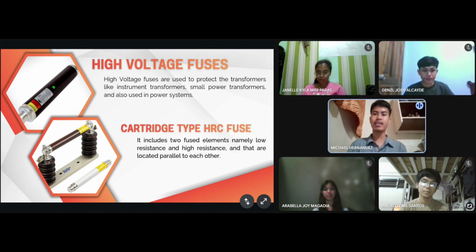Let's talk about the high voltage fuses. High voltage fuses are used to protect transformers like instrument transformers, small power transformers, and are also used in power systems.